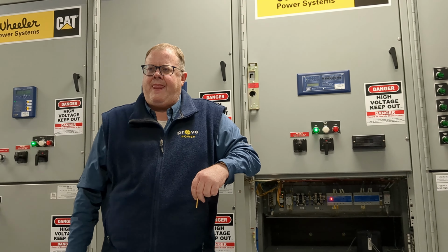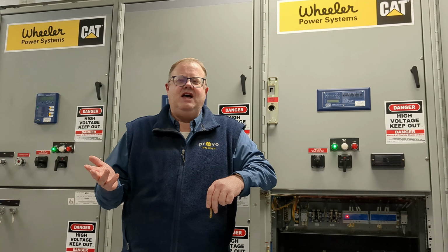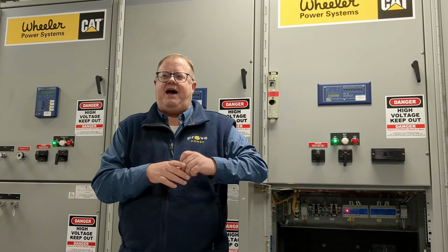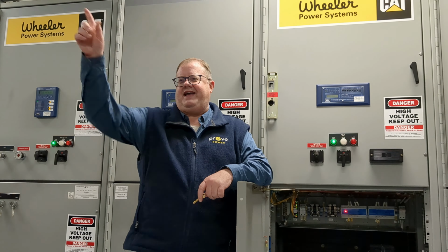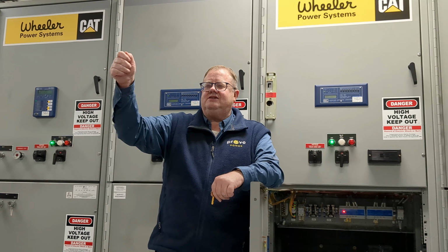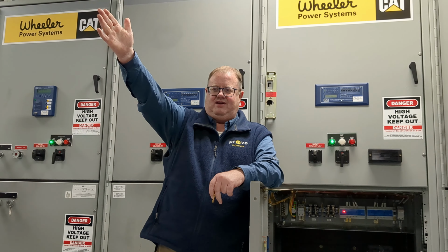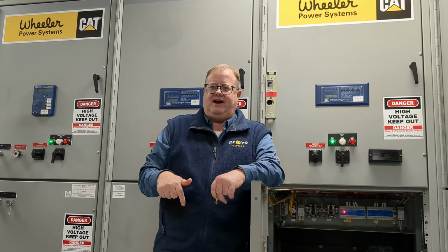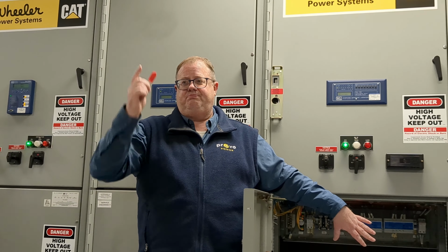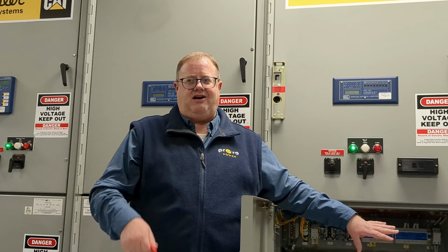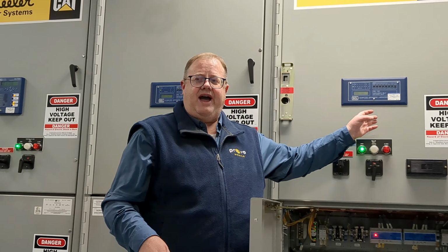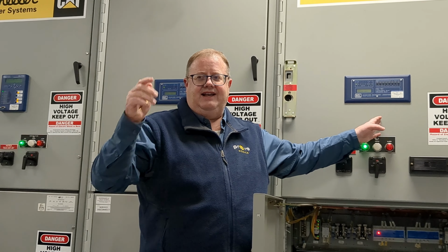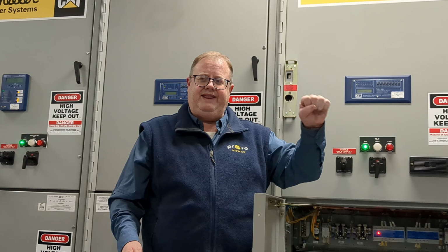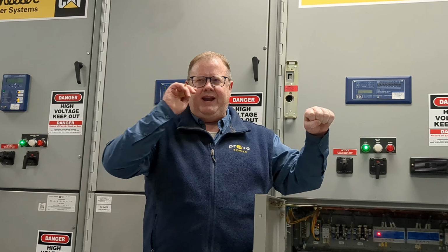How often do you run into, or do you have it be tripped? Well, how often do you have power outages? When the power goes out, what's happening is this. So like out here, he was trying to do a direct short. So if you're out on the line and a tree falls into a power line and it takes the power to ground, right? What happens is we design the system so first the breaker opens, boom, boom. So you'll see the breaker open, it's a big loud boom, boom, and then we'll have a delay for a second and then it'll close. And then it'll hold in that power for a certain amount of time, waiting for that fuse to blow.